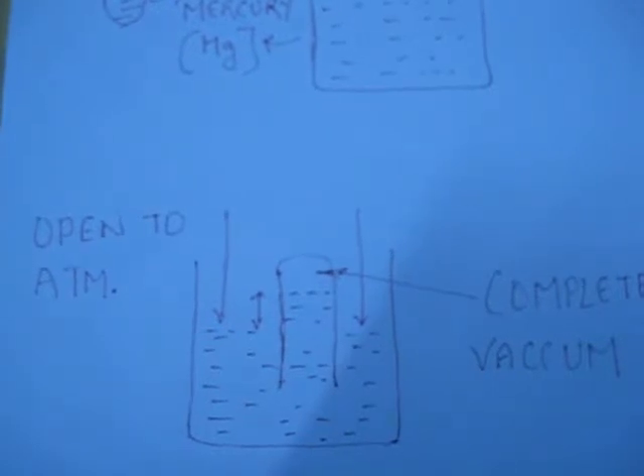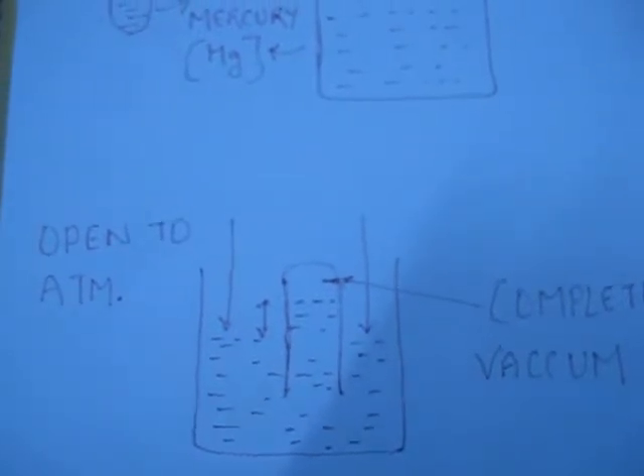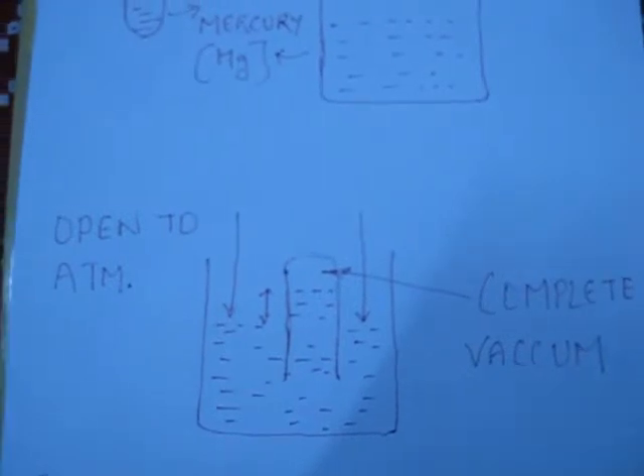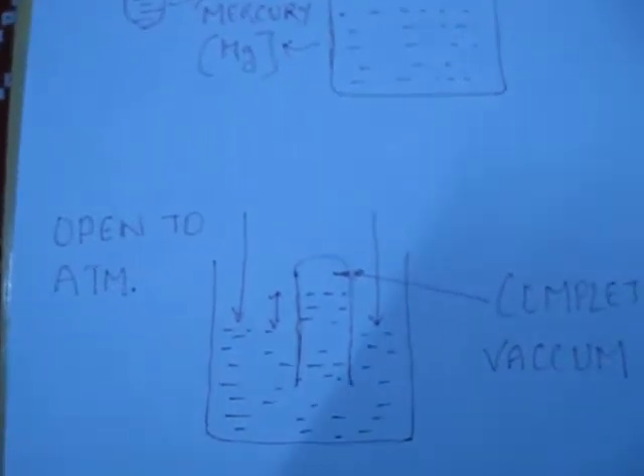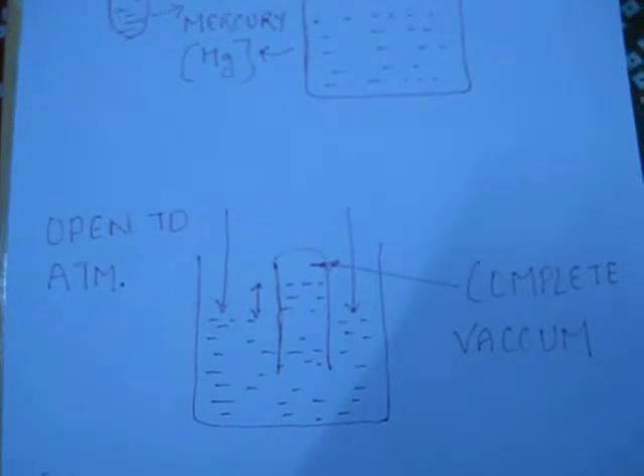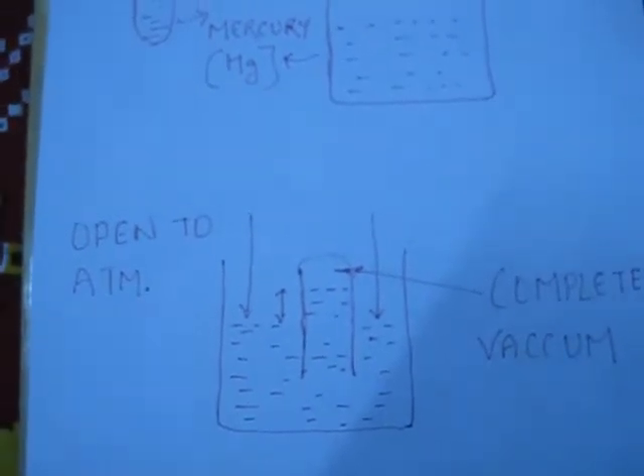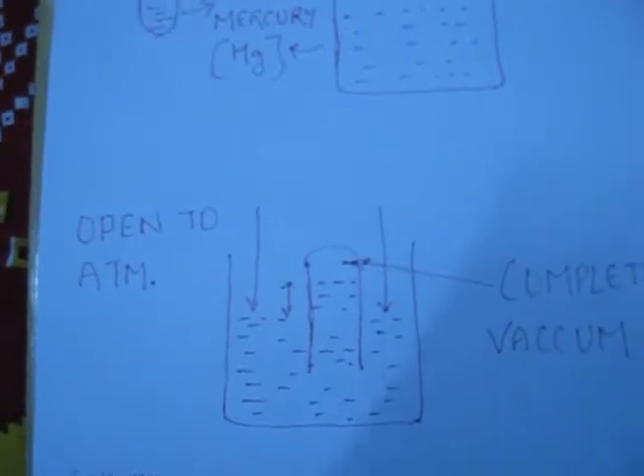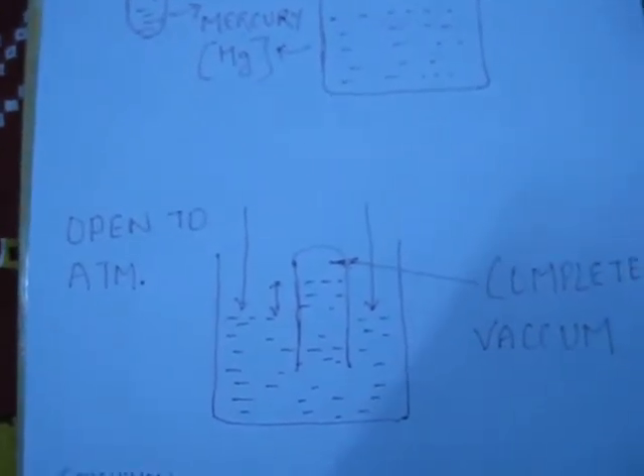Similarly for water, sucking water making complete vacuum, you can only suck a maximum of 10 meter, and that too in case of complete vacuum. Now any pump, like piston pump or centrifugal pump, never makes complete vacuum. Like, it on a best case makes 98, 95 percent vacuum.